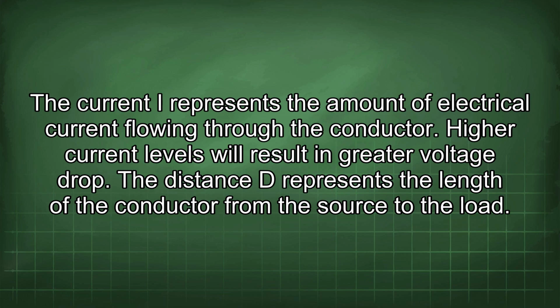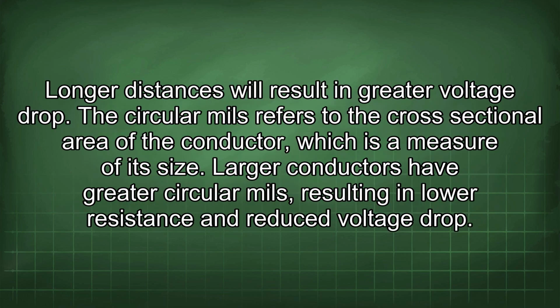The distance D represents the length of the conductor from the source to the load. Longer distances will result in greater voltage drop. The circular mils refers to the cross-sectional area of the conductor, which is a measure of its size. Larger conductors have greater circular mils, resulting in lower resistance and reduced voltage drop.